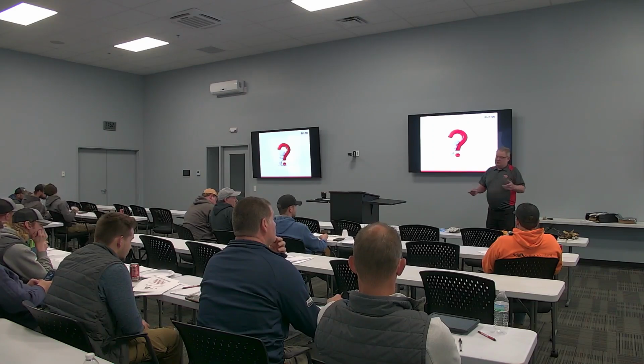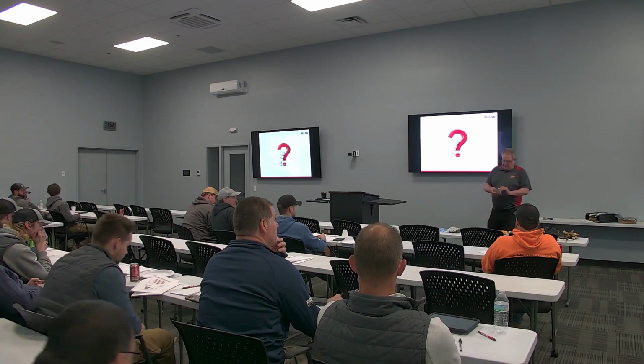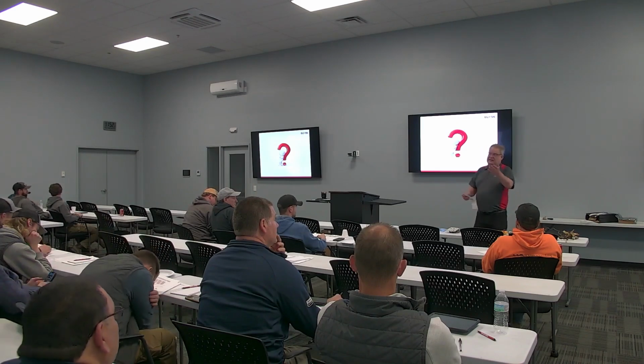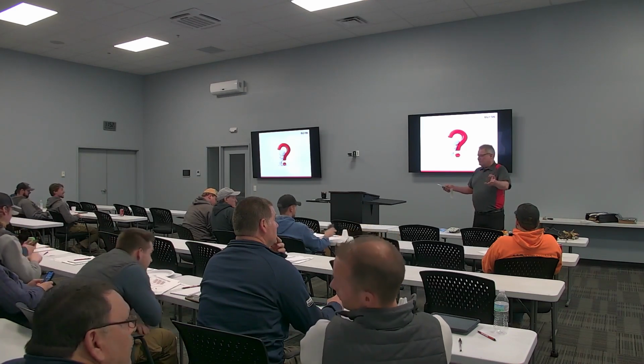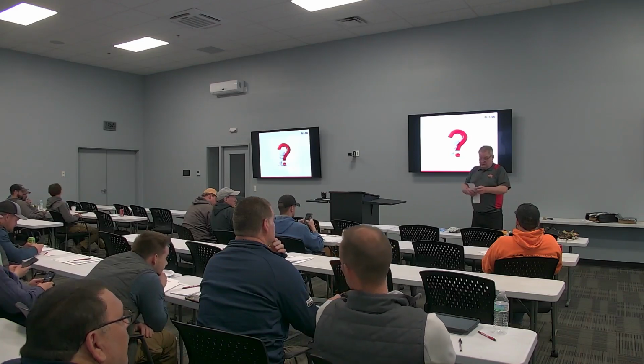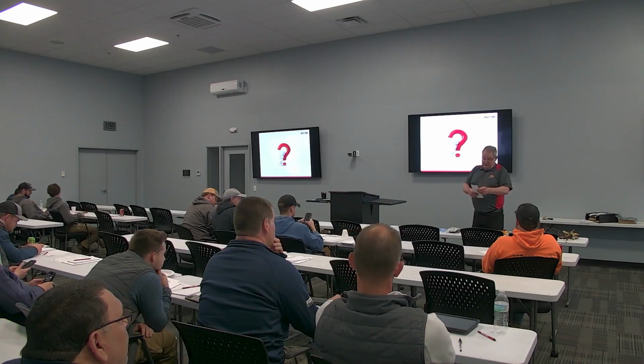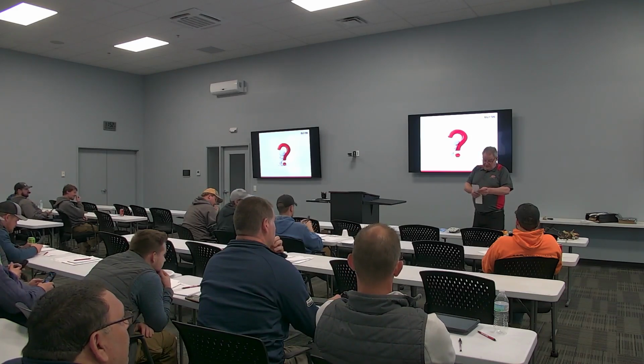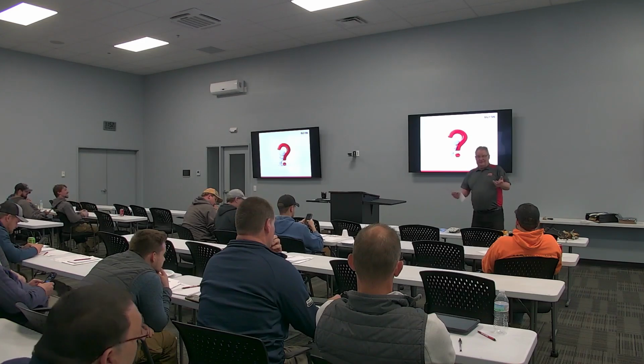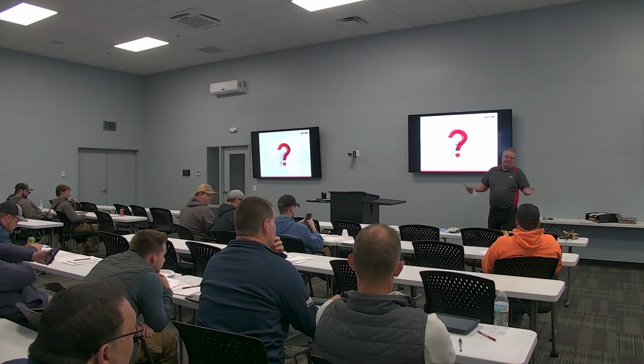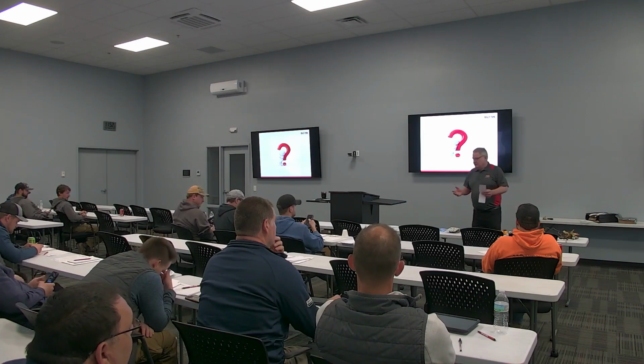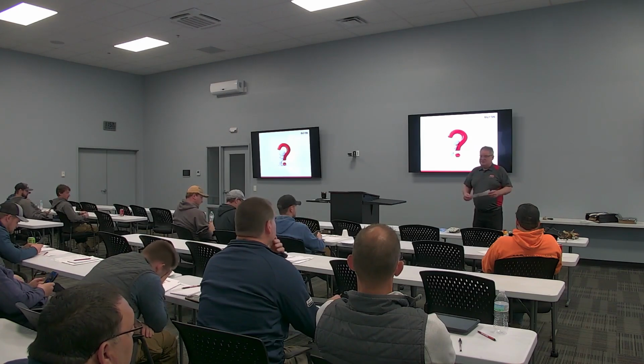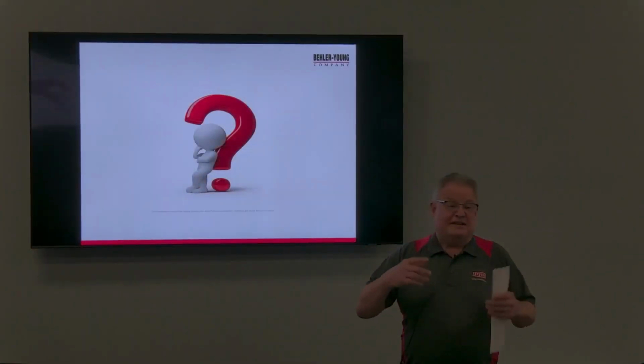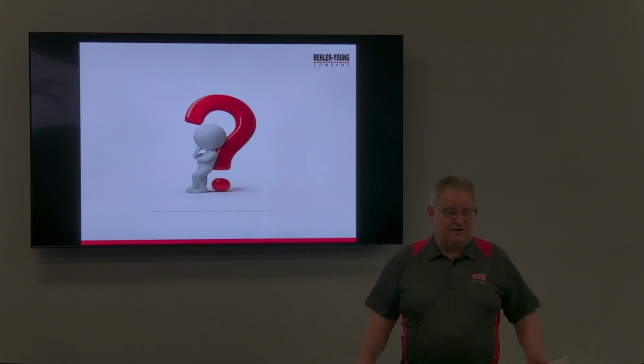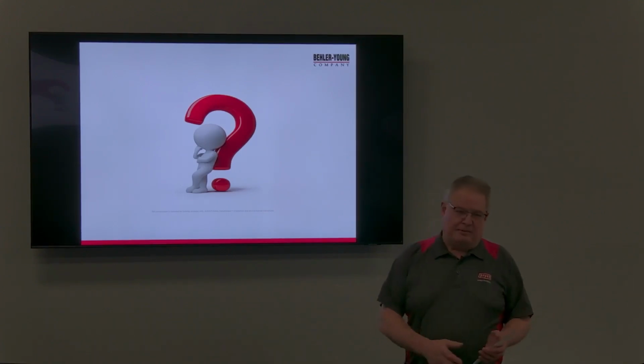Everything's going to perform. The only thing you're going to see different is the pressures are slightly less. For instance, 410A at 118 PSI, that sounds like a pretty normal suction pressure, 118, 120. 454B at 40 degrees is 107. So instead of 118 suction, we're going to have about 107, 108. So it's really going to be very close. But that's a good question. That's also why we have to liquid charge, because we got to make sure they come out of the can in the proper mixture.